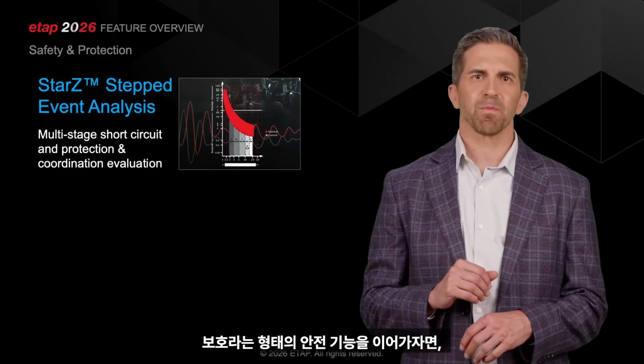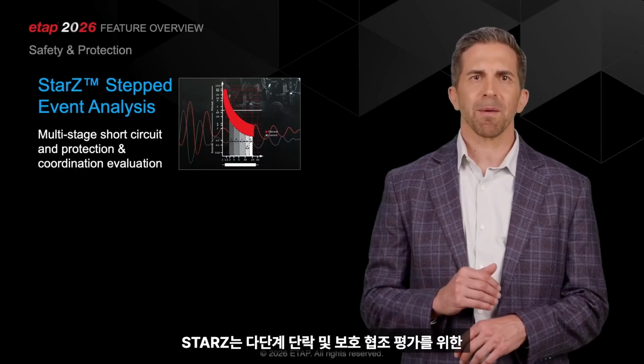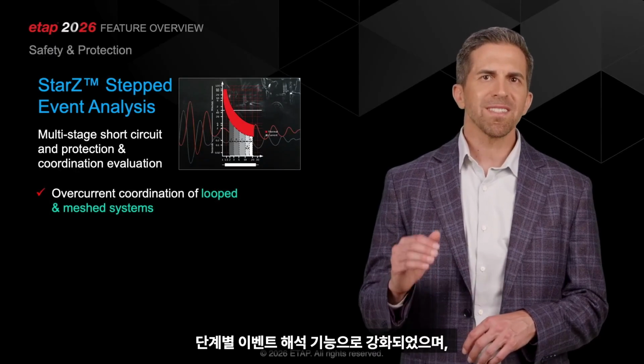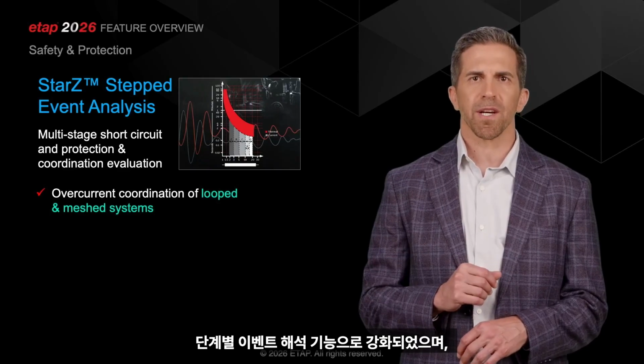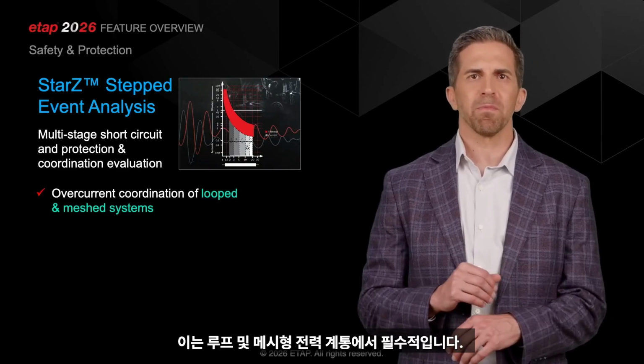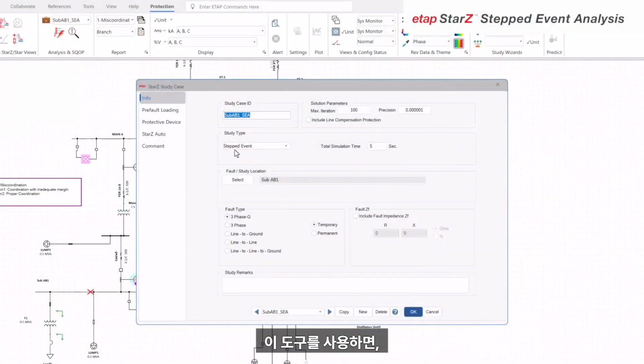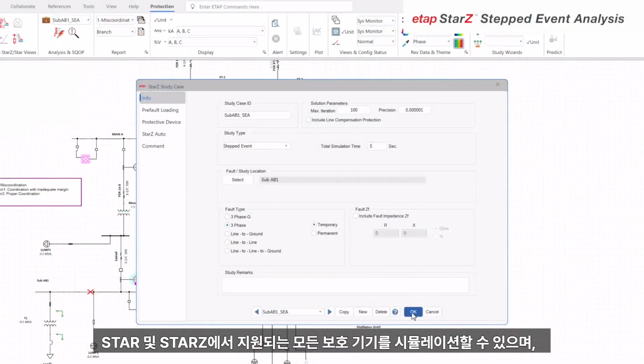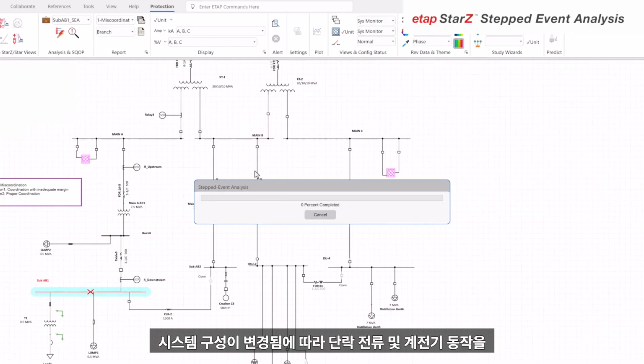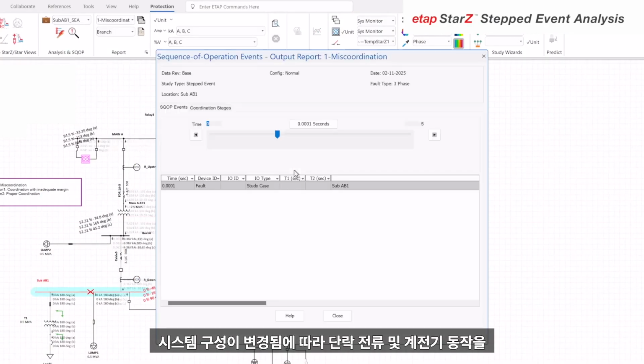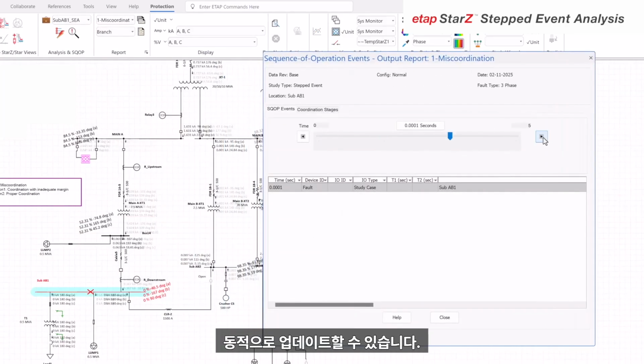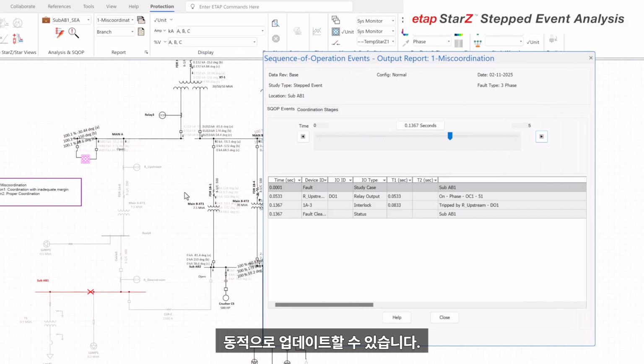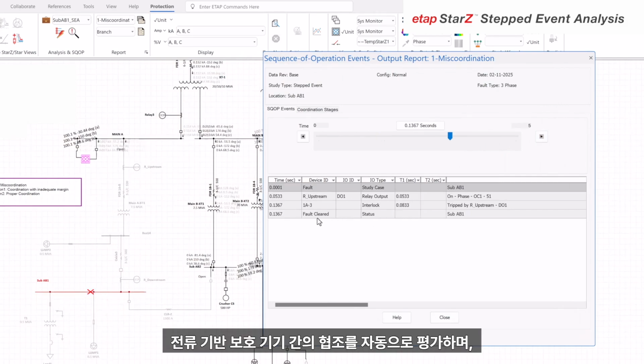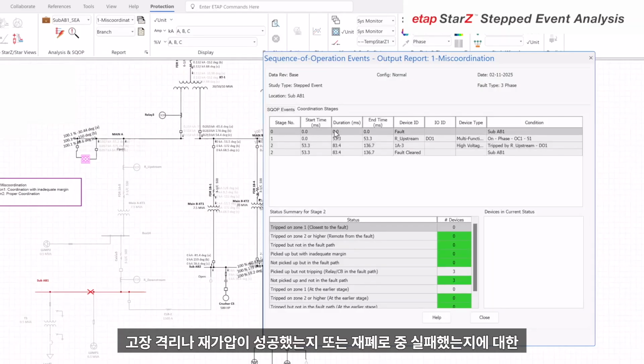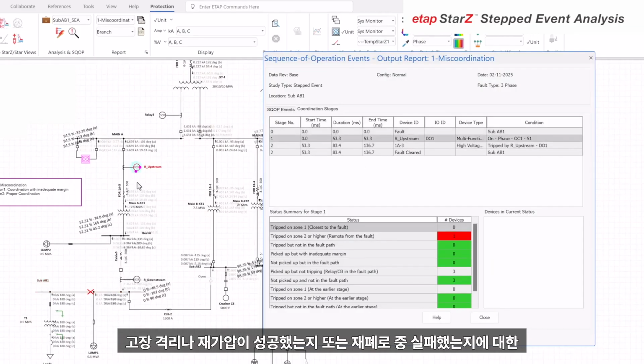Continuing with safety in the form of protection, Star-Z is enhanced with stepped event analysis, for multi-stage short circuit and protection and coordination evaluation, which is essential in looped and meshed power systems. With this tool, you can simulate all protective devices supported in Star and Star-Z, while dynamically updating short circuit currents and relay operation as the system configurations change. It automatically evaluates coordination between current-based protective devices and provides clear notifications when fault isolation or re-energization succeeds or fails during reclosing.